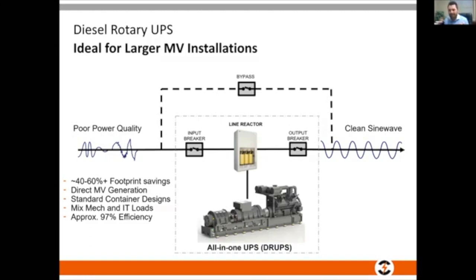By virtue of the installation, it's going to be massive. So I think for 35 kV type installations, what we'll probably do is have a transformer between our reactor and our machine. And so for the very high voltage solutions, we will have a transformer. If you go over to California, Silicon Valley, mainly it's 15 kV distribution. So for the project that I spoke about earlier that CCI supported us, it was 15 kV direct generation, 25 megawatts, just a standard parallel redundant.